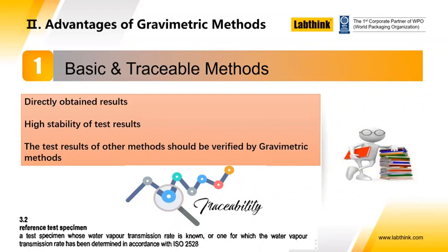And part of the traceability of the method relates to the use of reference test specimens. So we can use reference films with this method for which we know what the transmission rate is under a given set of temperature and humidity conditions. We can use those reference films to verify that the machine or the method is working accurately. And in that way, you can use ASTM E96 as a verification method or a validation method, or if you like, an arbitration method.